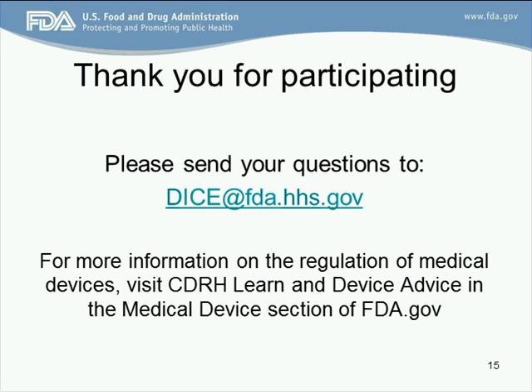Good afternoon. Thank you. I do a lot of work with point-of-care devices, and so we're working with whole blood devices. Usually we have a point-of-care predicate and a laboratory analyzer as a reference analyzer. Now, since the point-of-care predicate would get us through points 1 through 4 in the flowchart, would it be reasonable to assume that when doing the accuracy studies, the method comparison studies, they be done to the reference, which is generally assumed to be closer to truth than another point-of-care device?